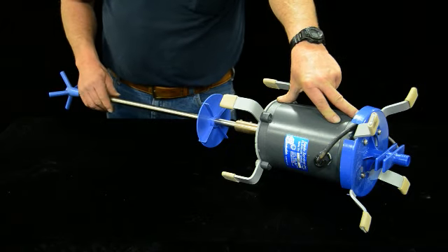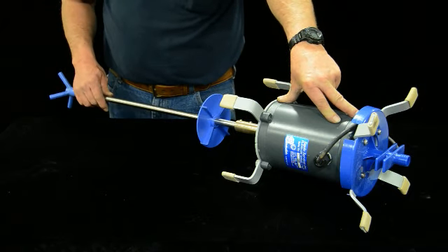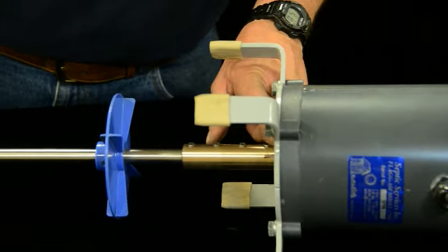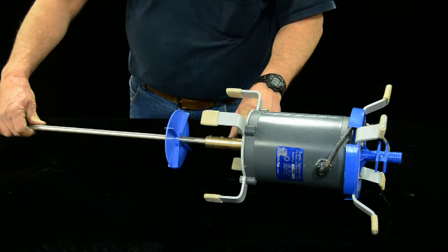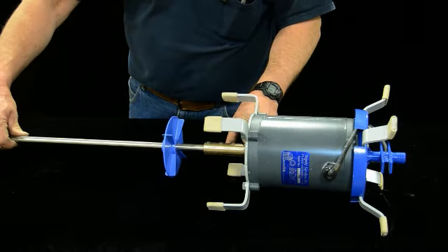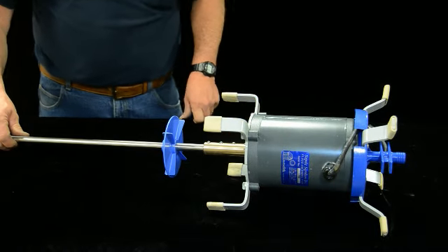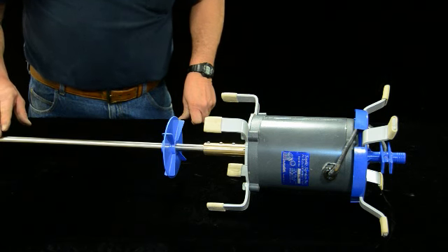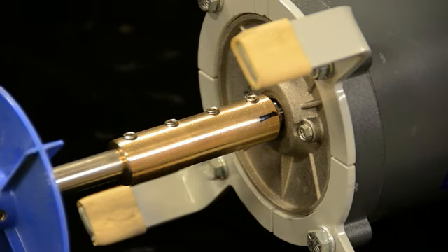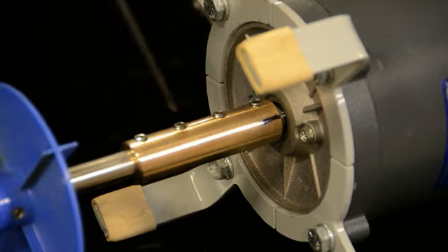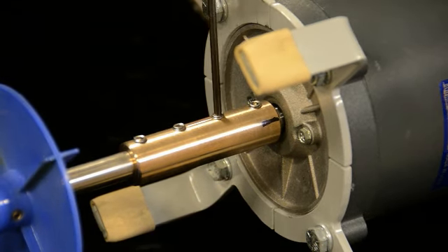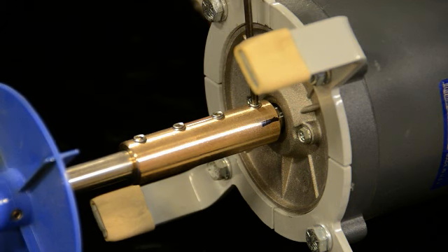When you're assembling one as a new one or reassembling it, generally speaking, most manufacturers have a line that you match up with both on the motor and on the counter shaft. You match that up because it's been balanced at the factory. You don't want to over-tighten it, because if you over-tighten it, then you throw it out of kilter. So just a little bit of snugness. You don't need to overdo it. Just an Allen wrench, a little bit of snugness, it'll stay in place for you.